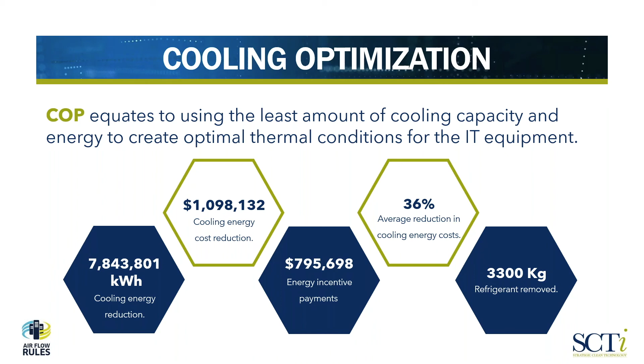To put a different perspective on it, our cooling optimization program has worked across a variety of data centers—colos, large data centers, small data centers. On the colo side, our average is about a 40% energy reduction, and we've averaged about 274 kilowatts of additional IT load, enabling this load to be added without requiring more cooling on site.